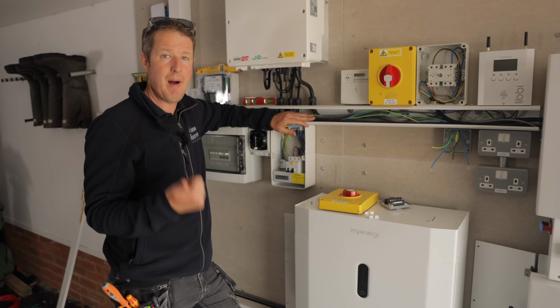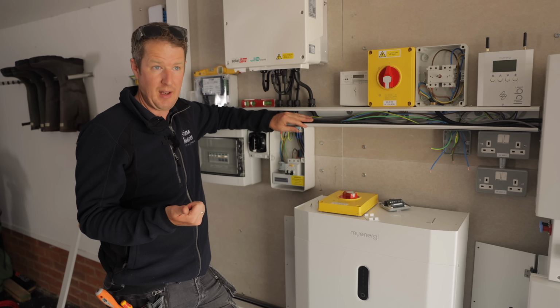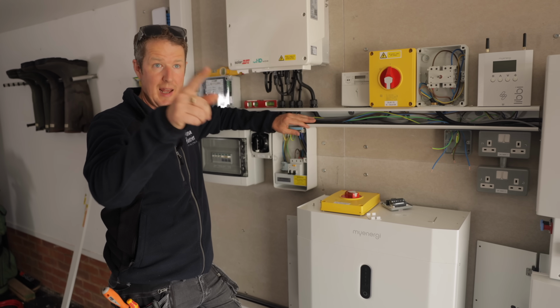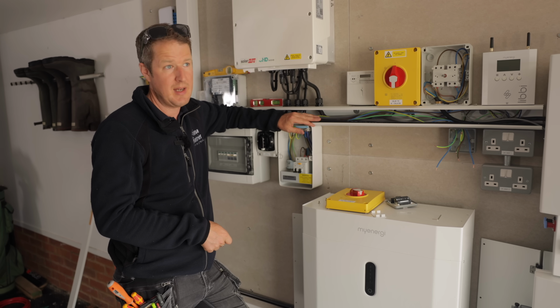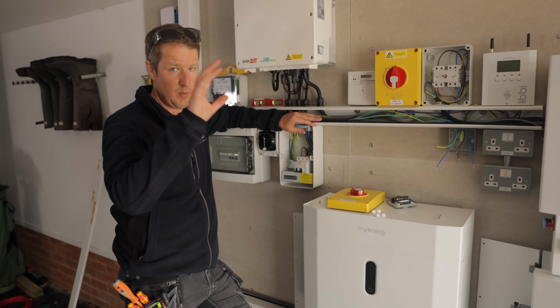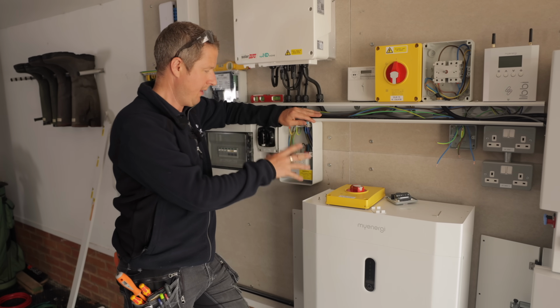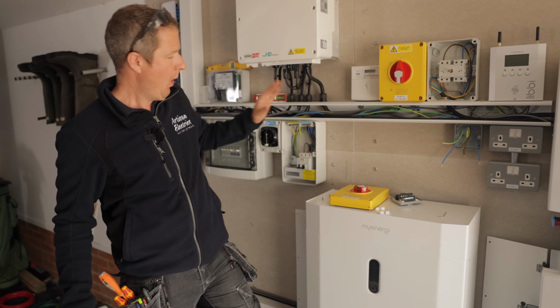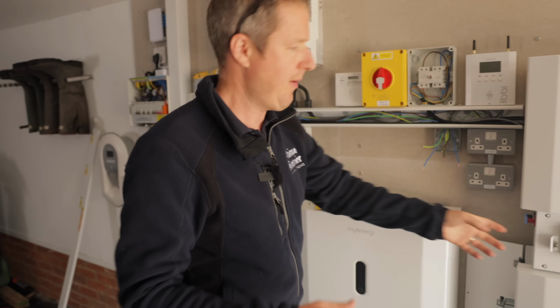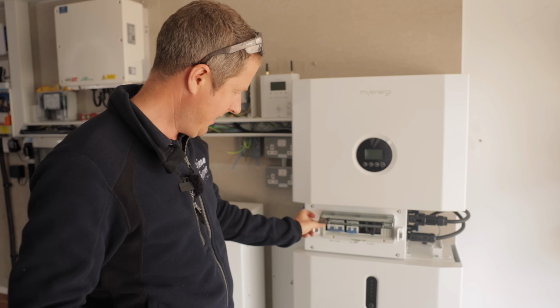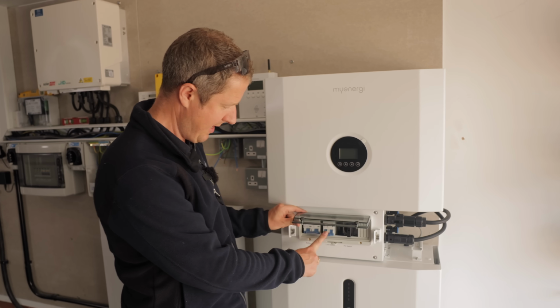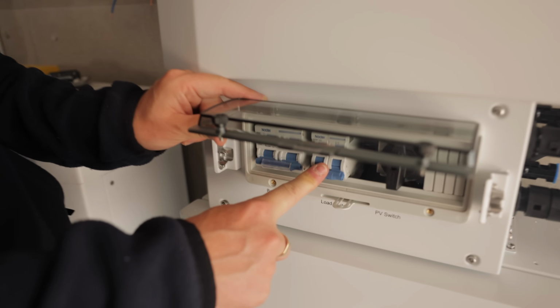Another important rule, you must have an alternative means of earthing. So we've installed an earth electrode, connected that to the main earthing terminal of the property, so that if the PME earth is lost, we've still got a good earth that this system can run off of. All of this is running off a 32 amp breaker here in the inverter. You can see that is the backup circuit breaker.